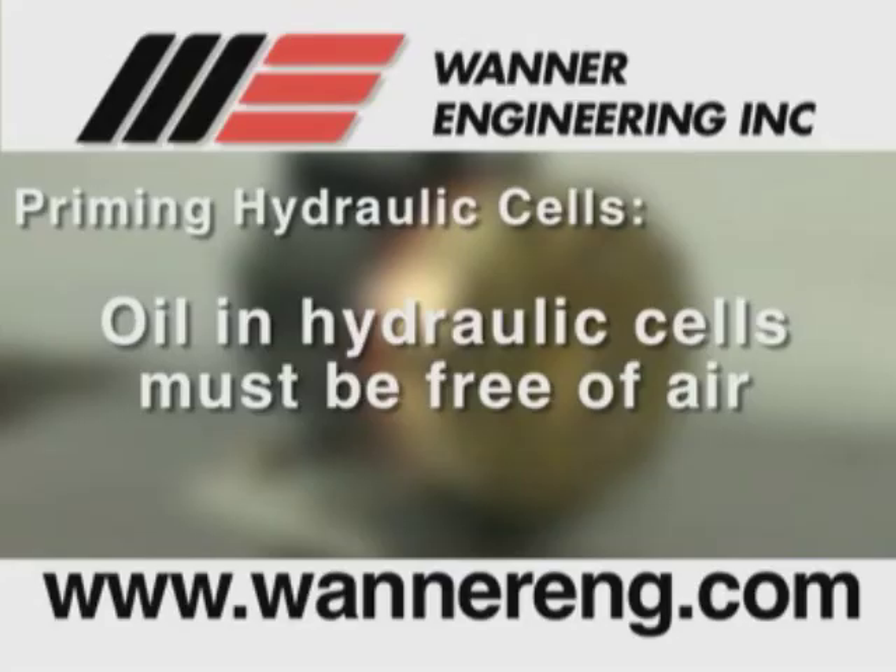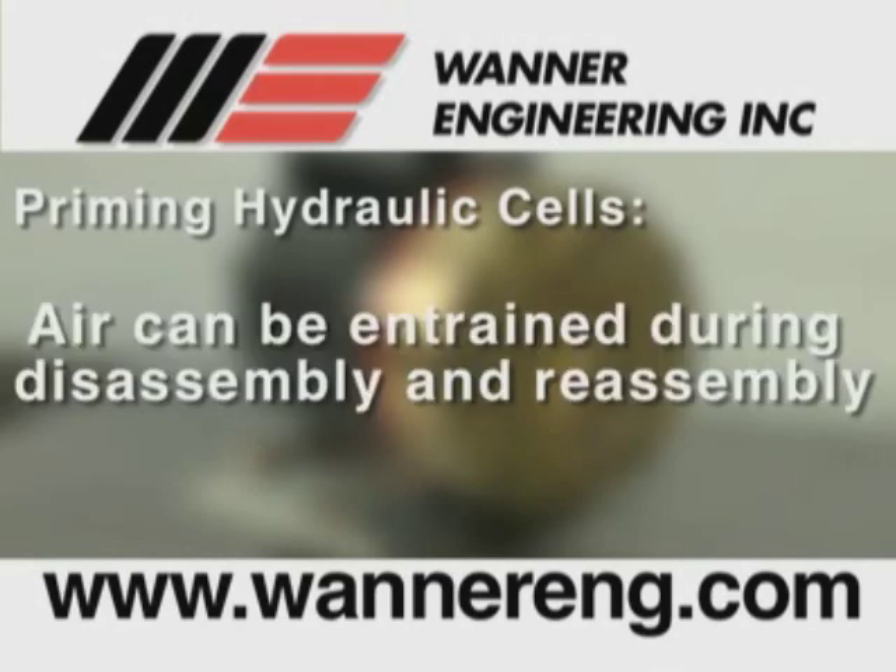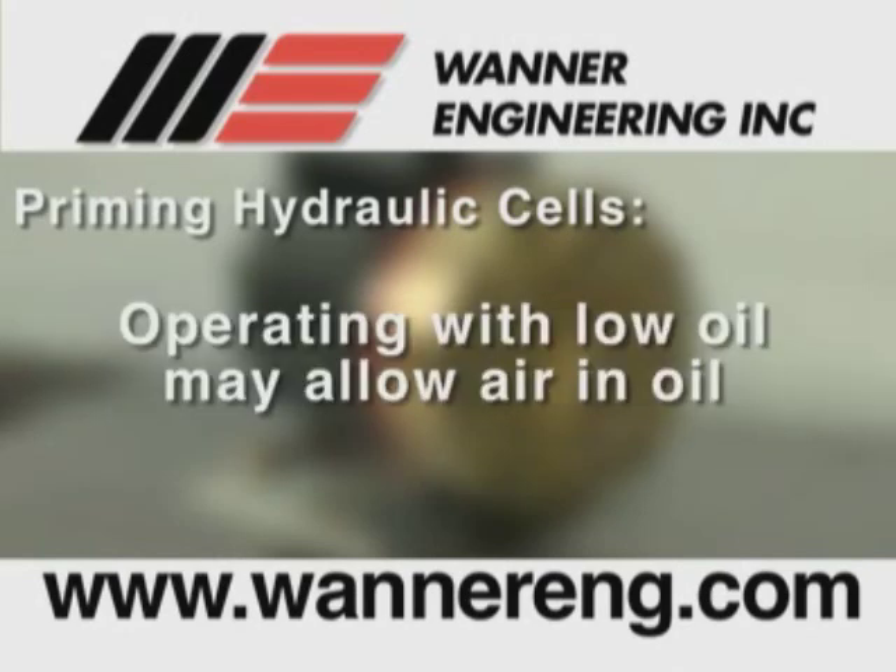In order for Hydra-Cell pumps to operate properly and deliver the proper performance, the oil in the hydraulic cells behind the diaphragm must be free of air. By priming the hydraulic cells, we remove that air to provide smooth, efficient performance for the pump. Air can become entrained in the hydraulic cells during disassembly and reassembly of the hydraulic end, or by operating the pump with a low oil level in the reservoir.